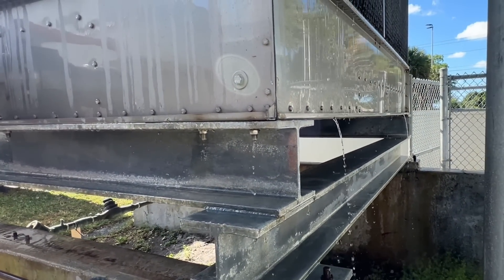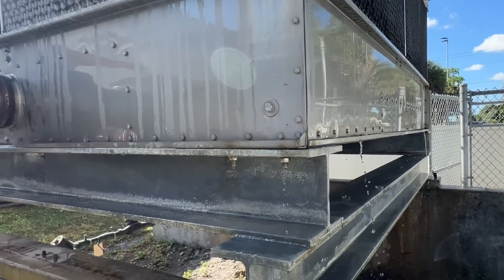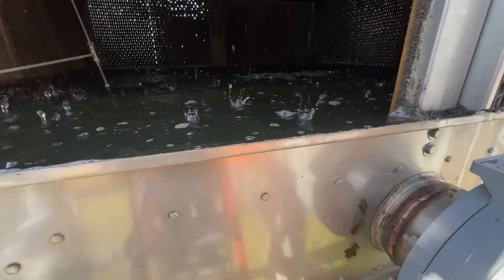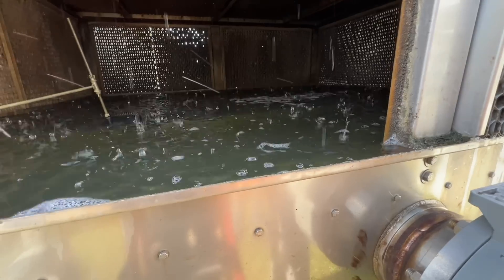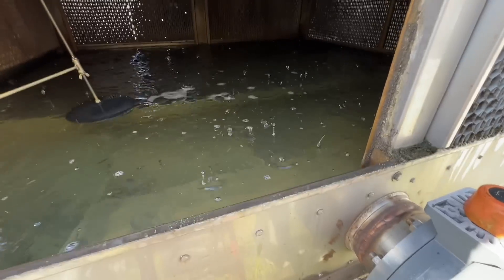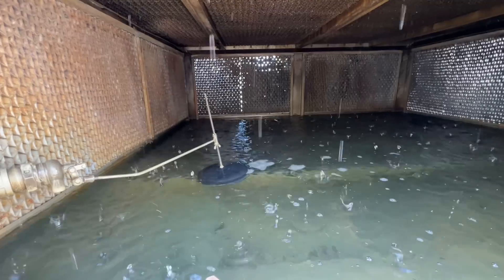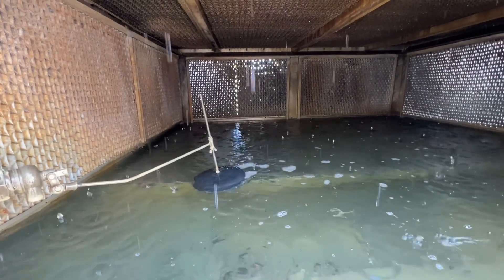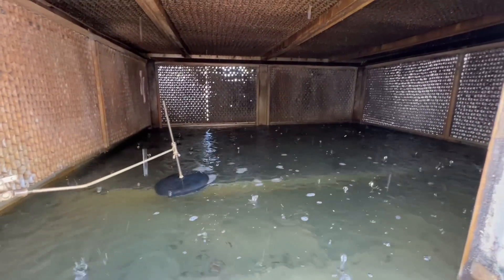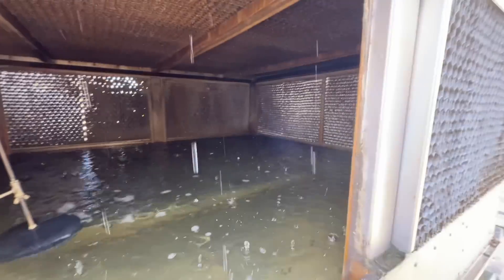Okay, it seems to be slowing down. We'll see if it comes to a stop and then I'll open that valve again. We're still pouring out the overflow but it's not getting any higher, so I'm going to open up that valve and see if this rises back up. That didn't seem to do anything. What I did is I just lowered the float level to about an inch, inch and a half or so, and we'll see if that keeps the level high enough so it doesn't drain the sump but not too high that it's overflowing.